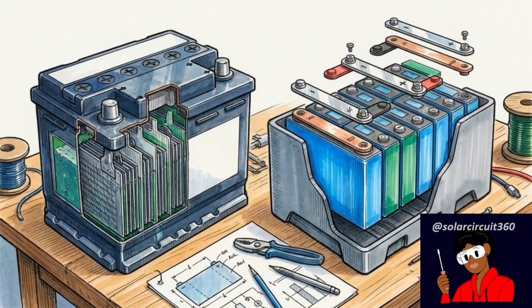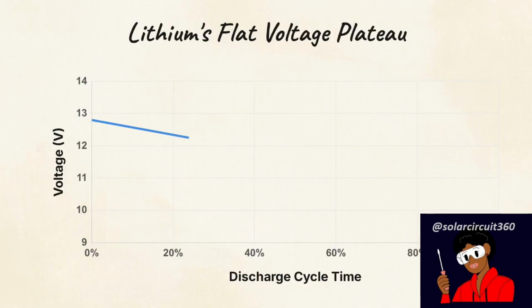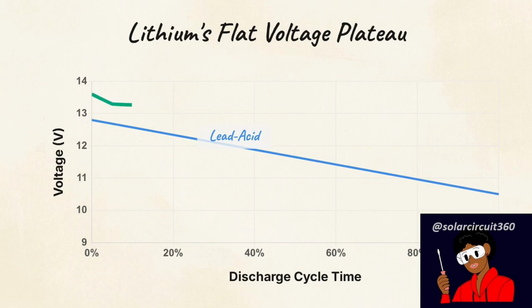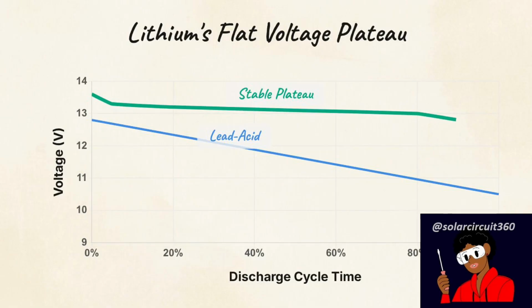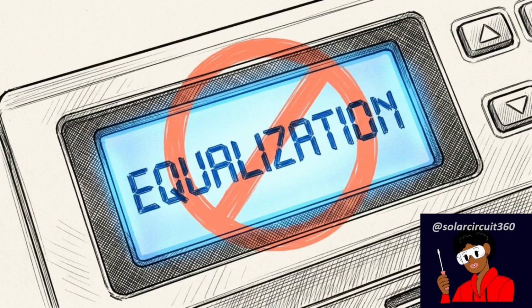The reason default settings fail comes down to the physical difference between how traditional lead-acid batteries and LiFePO4 batteries release energy. This graph shows a standard lead-acid discharge curve. Notice the steady, sloped downward trajectory. Plotting a LiFePO4 battery, the behavior changes completely. It maintains a highly stable, flat voltage plateau for 90% of its cycle before a steep drop-off. Because lithium chemistry holds this flat voltage, legacy lead-acid charging modes like equalization or prolonged float charging are completely incompatible.